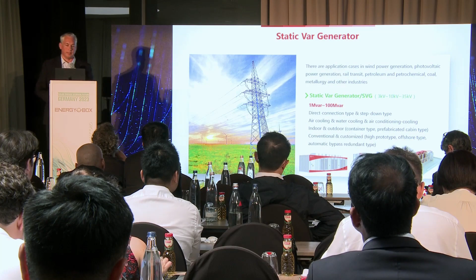Static VAR generators are another important piece of equipment. This device is used to improve the power factor of the load. They are used in highly dynamic loads where the power factor fluctuates rapidly or in big steps, like solar inverters and wind turbine generators, and are also present in railway electrification systems, cranes, manufacturing machinery, and so forth.